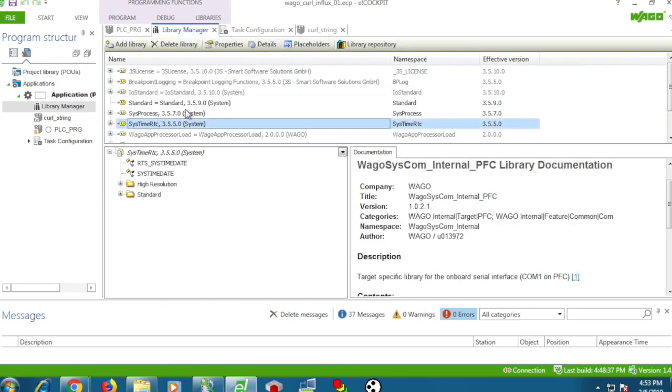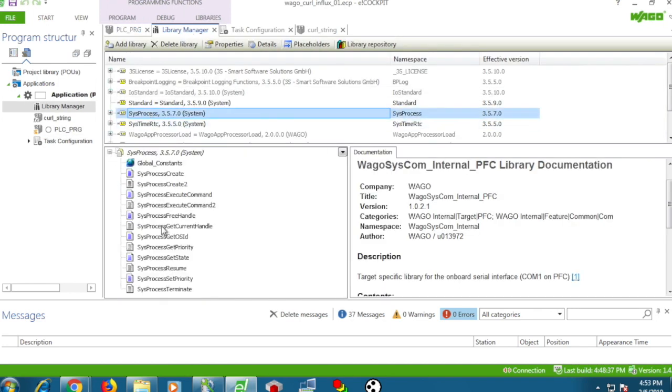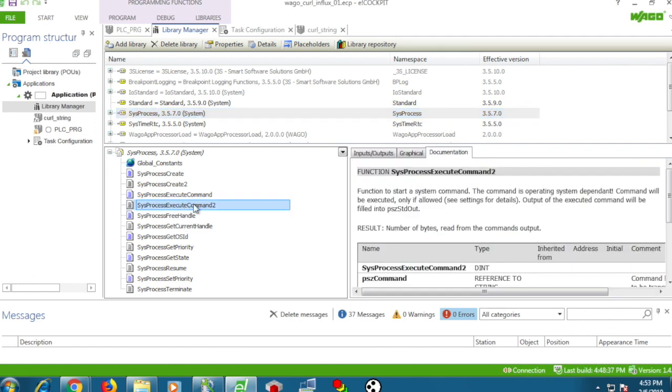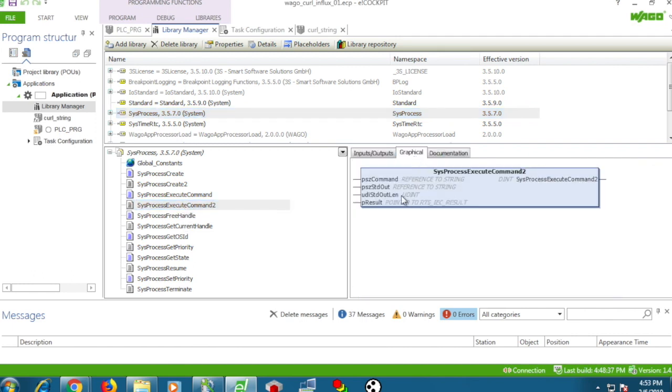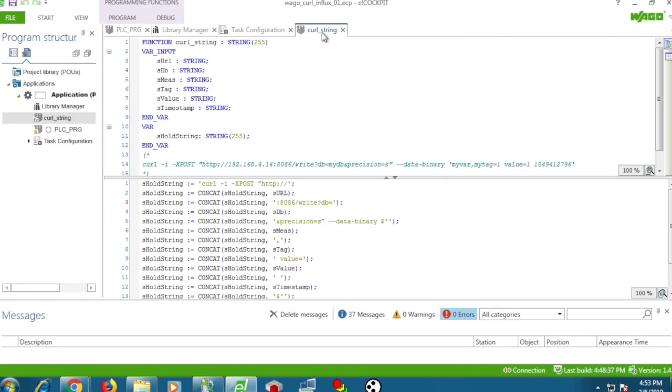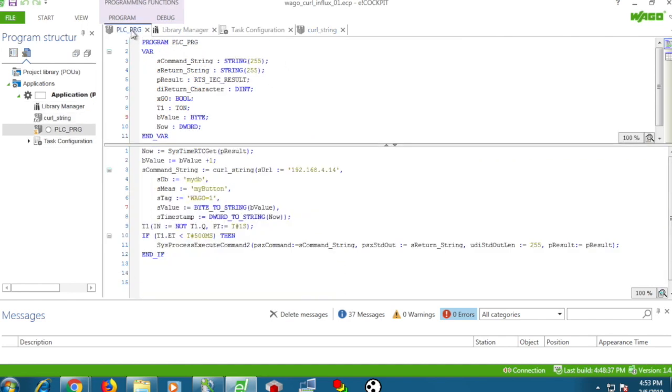To do that, we're using the sysprocess library. There's an execute command 2 that lets you pass a command line to the Linux shell. This is the function that basically concatenates all of our tags and creates the string.